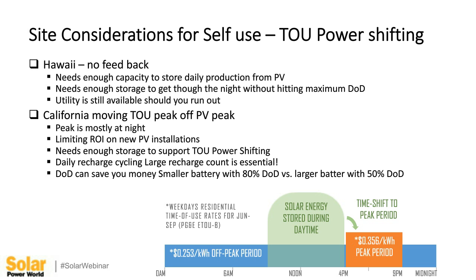When using batteries like this, the daily recharge count is very important. This is why you're typically not using lead-acid batteries, because the recharge count is lower, at least on traditional lead-acid batteries. You're going to be looking at lithium iron phosphate as your best option for this because it's got a much higher recharge count. Lithium ion also works very well. You can use a slightly smaller battery as far as total capacity goes, again because of the depth of discharge allowed with lithium technology chemistries versus lead acid.